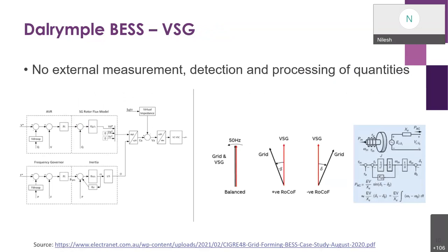As we understand, this battery operates in a virtual synchronous generator mode. In terms of its functionality, there are two levels of control, a primary and a secondary, and the heart of the primary controller is virtual synchronous generator mode. It is a combination of grid forming mode, synthetic inertia, frequency control, rotor flux dynamics, and AVR. This component emulates a synchronous generator during both steady state and transient conditions. The secondary control is more for site-specific need, automation, and functional logic.